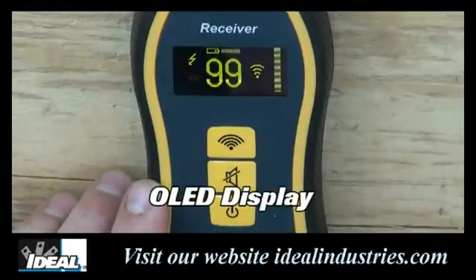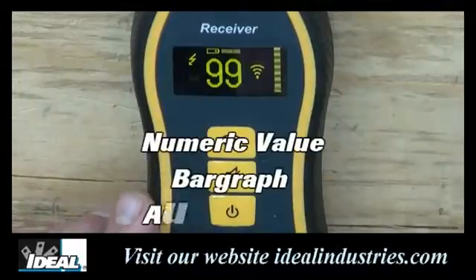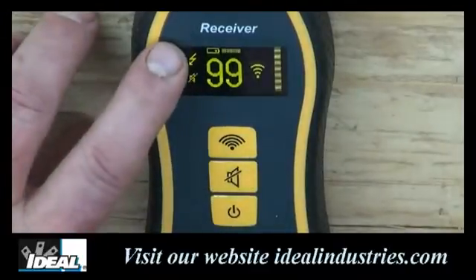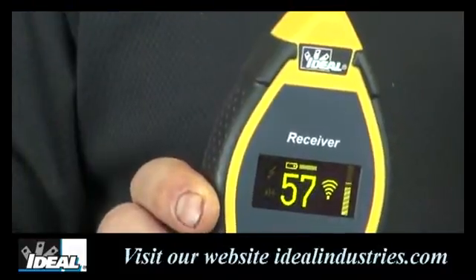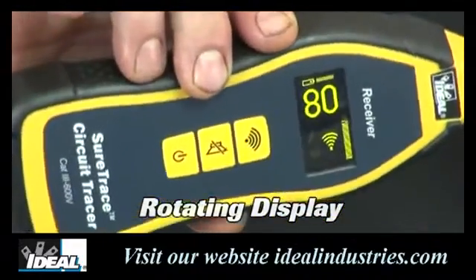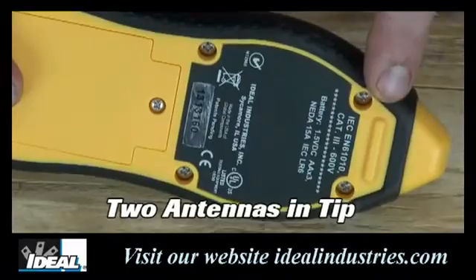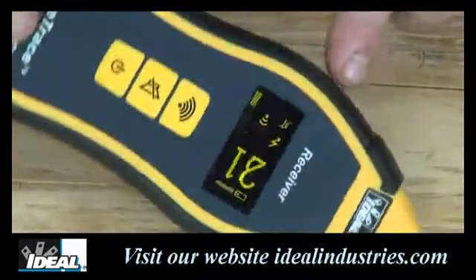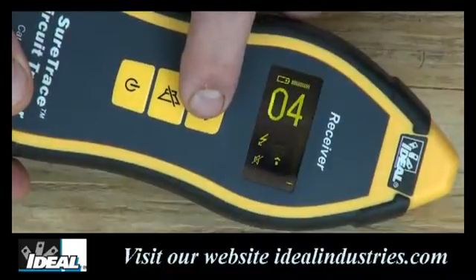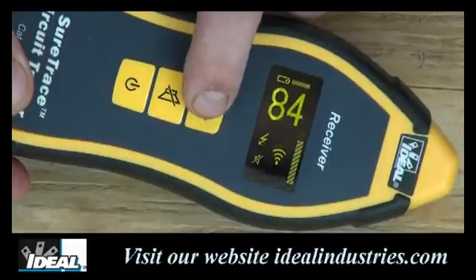The receiving unit has a bright organic LED display and indicates when the transmitting unit detects power present via a lightning bolt symbol. The numeric value, bar graph display, and audible signal — which can be turned on and off — provide quick and easy tracing feedback. A battery symbol at the top of the display indicates when the battery is running low. One great feature is that the reading rotates to stay upright however you hold the tester, which is really convenient when tracing wires. There are two antennas in the tip for tracing wires in walls, and one in the front for finding breakers in panels. The tester has four sensitivity modes with resolution from 0 to 99. Generally start at the highest sensitivity setting and use lower settings to verify you're on the correct cable.